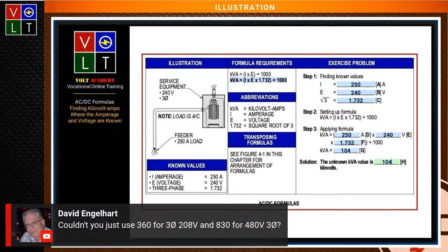Somebody had a question up in there. So couldn't you just use a 360 for three-phase 208 and 830? Yeah. And actually, for the 480 volt three-phase, we use 831 because we round up to the next one. Instead of 830, we do 831. And then for the 240 three-phase, we do 416.